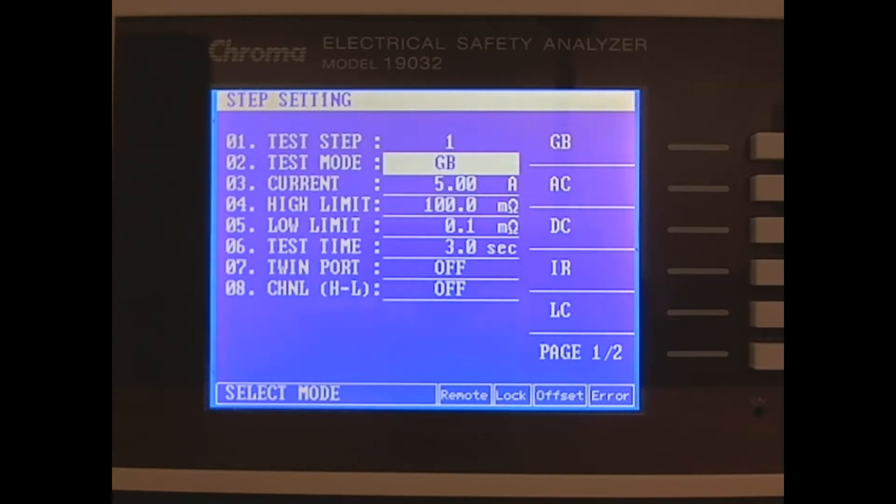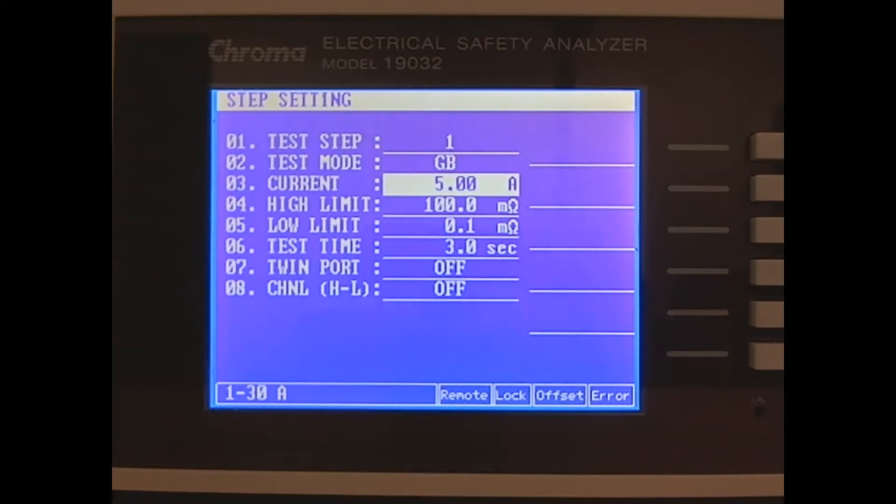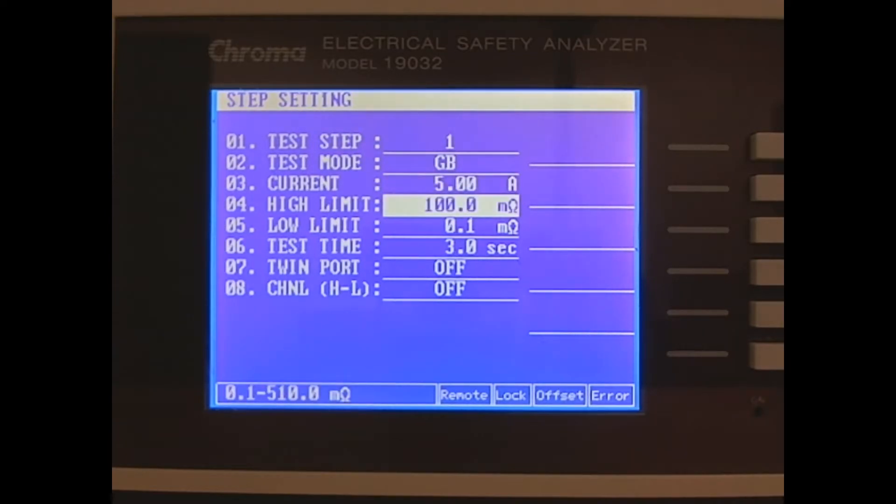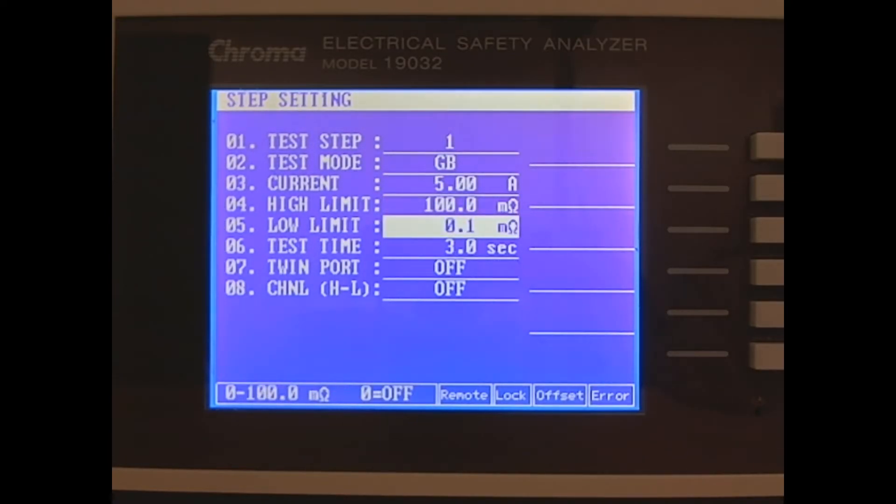We'll set our constant current to 5 amps and choose our pass-fail limits of 100 milliohms and 0.1 milliohms. Finally, we'll leave our test time to the default of 3 seconds.